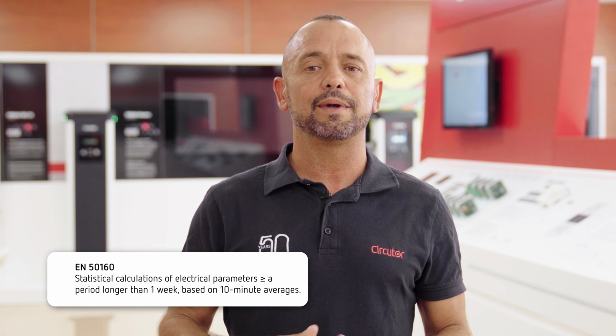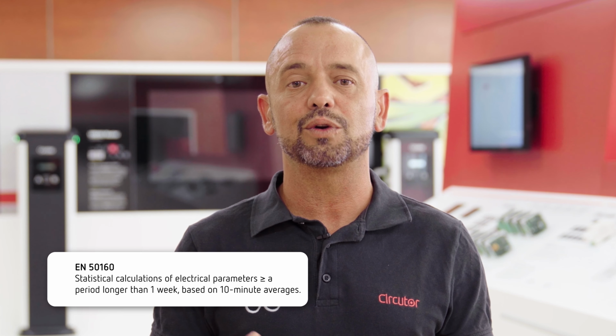EN 50160 is a European standard that defines the recommended levels of power supply quality in distribution networks under normal operating conditions. It is based on statistical calculations of certain electrical parameters, which are usually recorded in 10-minute intervals over the course of a week. This standard is used as a technical reference so that utility companies can guarantee a stable, safe and reliable service to consumers.